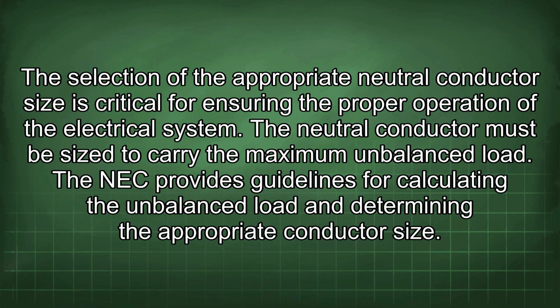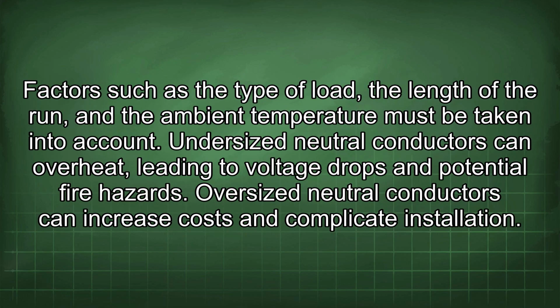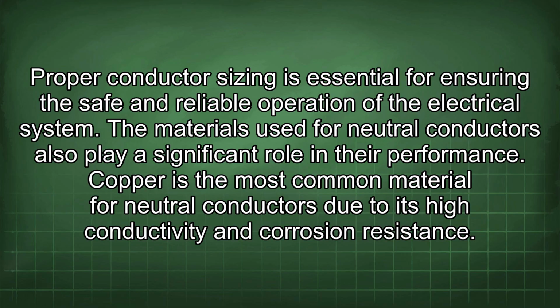The selection of the appropriate neutral conductor size is critical for ensuring the proper operation of the electrical system. The neutral conductor must be sized to carry the maximum unbalanced load. The NEC provides guidelines for calculating the unbalanced load and determining the appropriate conductor size. Factors such as the type of load, the length of the run, and the ambient temperature must be taken into account. Undersized neutral conductors can overheat, leading to voltage drops and potential fire hazards. Oversized neutral conductors can increase costs and complicate installation. Proper conductor sizing is essential for ensuring the safe and reliable operation of the electrical system.